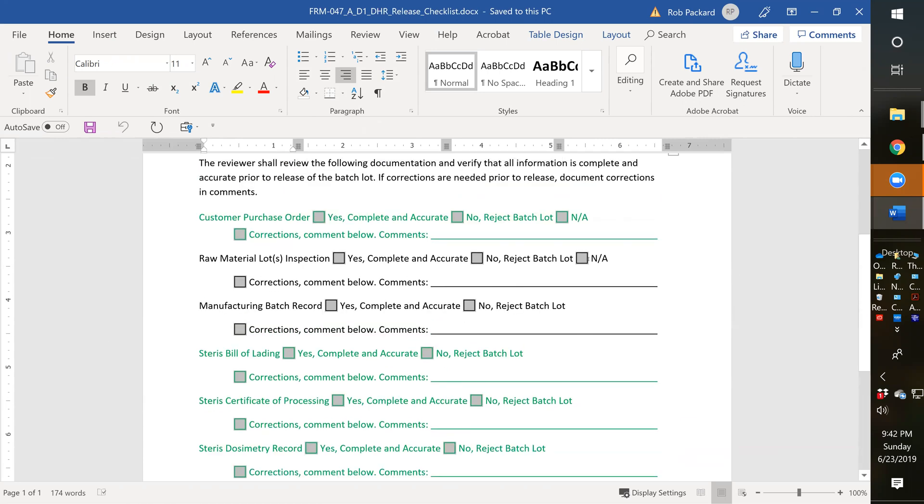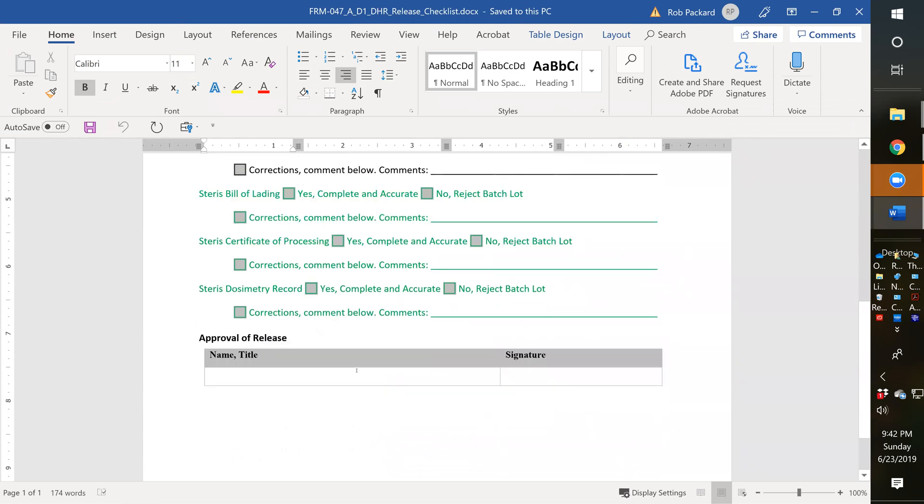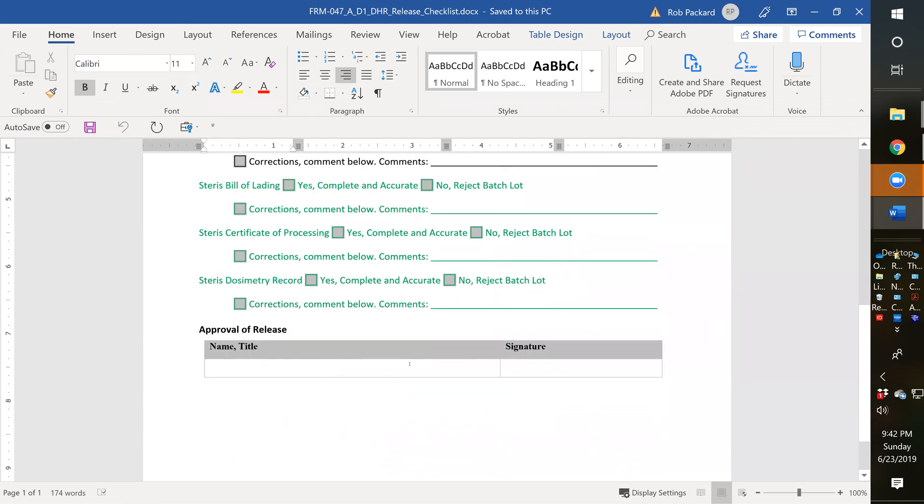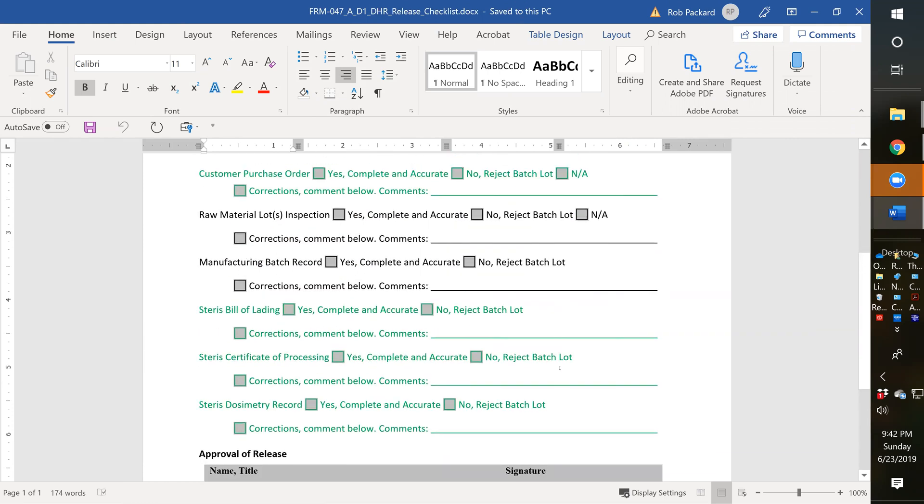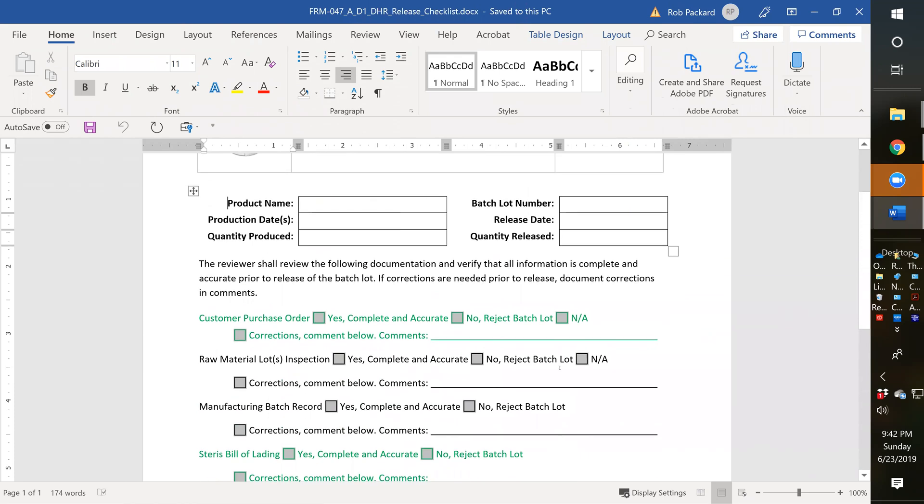The only thing that's going to be not applicable is up here where you have NA if it's actually incorporated into the batch record or you don't have any lot materials. At the bottom, we have a signature and the name and title of the person. You actually have to have a signature releasing your product - that is one of the requirements in the FDA QSR.